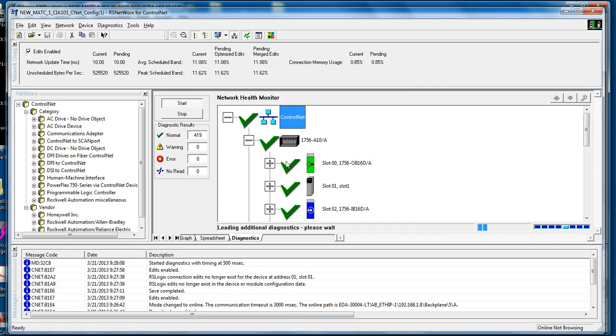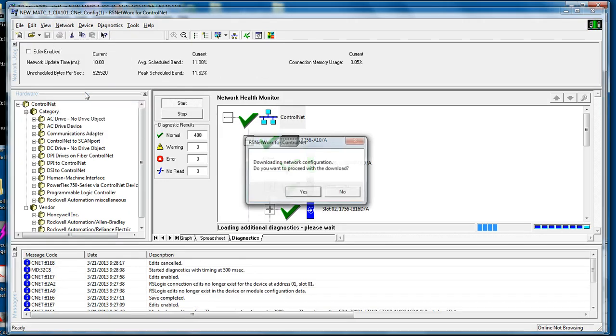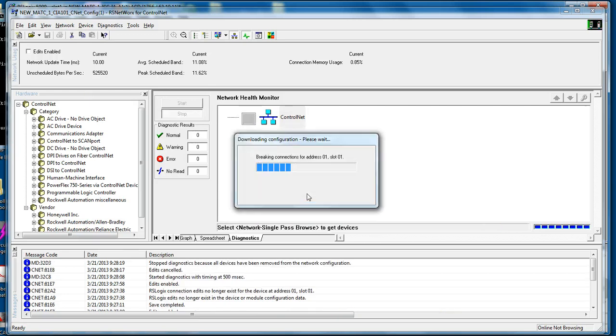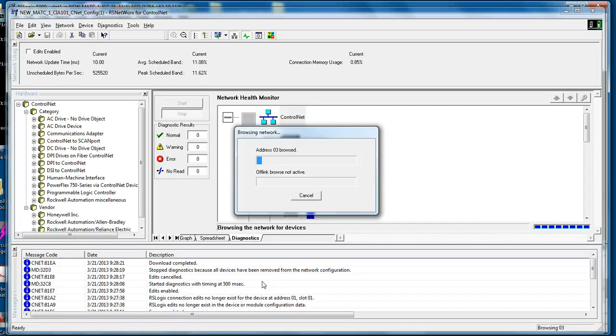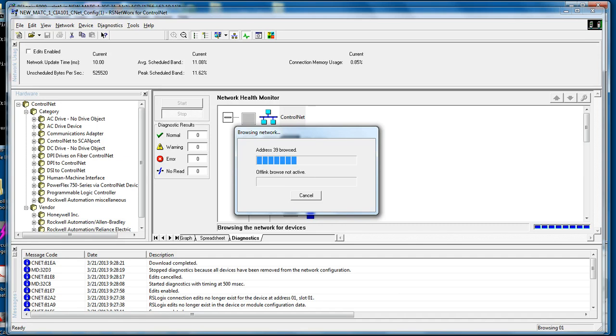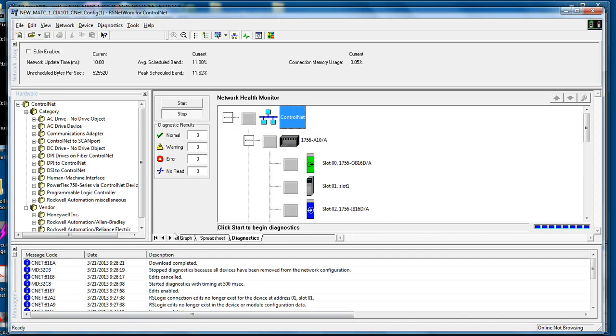Now that this has all been checked out, we can go to Network and say Download to Network. This will update the ControlNet keeper file and schedule the ControlNet so that all items will schedule and run and communicate. The download has completed. You can see down here in the message codes that these devices have been updated, the address configuration now matches.